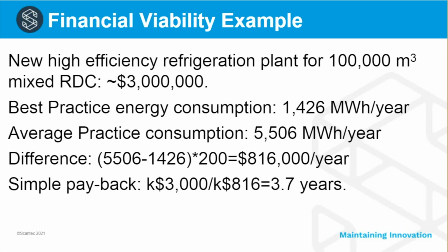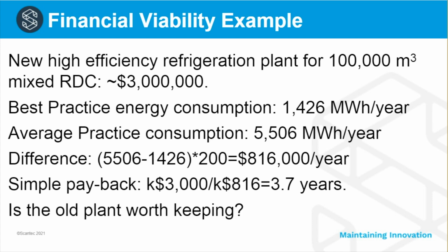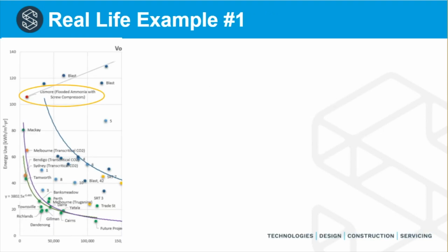Now, even if you were paying less than that, let's say $100 per megawatt hour, it is still a lot of money, and it would still provide a reasonable return to pick a high energy efficiency refrigeration system, because it frankly does not cost a lot more than a conventional liquid overfeed system. So is a conventional plant worth keeping? Well, personally, I think not. This is another real life example.